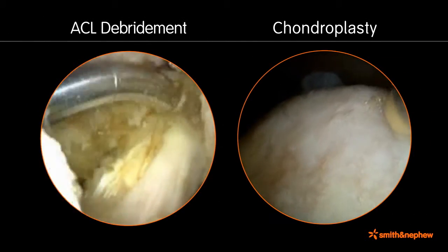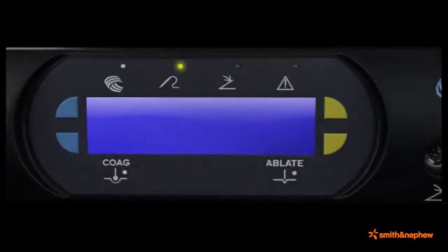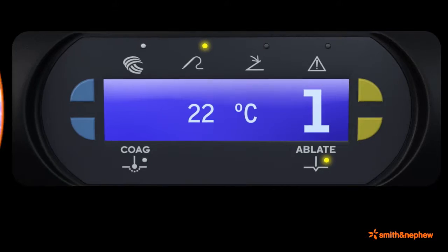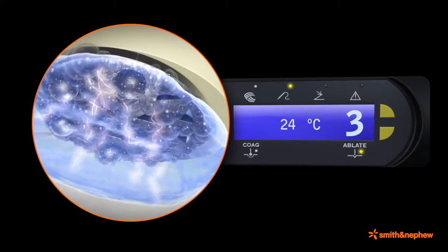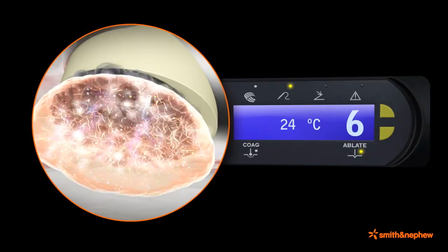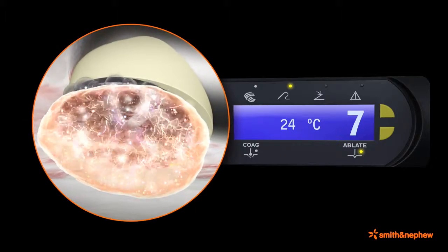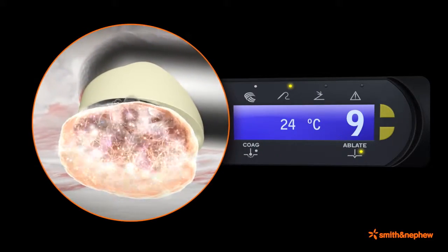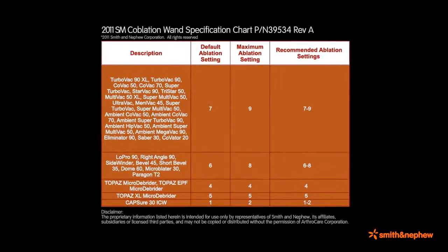Smith and Nephew Coblation products are designed to operate in ablation and coagulation modes, which result in different tissue effects. As the controller settings increase from 1 to 9 in the ablation mode, the performance of the wands transitions from a thermal effect to an ablative effect through the creation and intensity of plasma. Depending on the wand design, the transition to plasma usually occurs between controller settings 2 to 7. Optimal use occurs at the default setting and above.